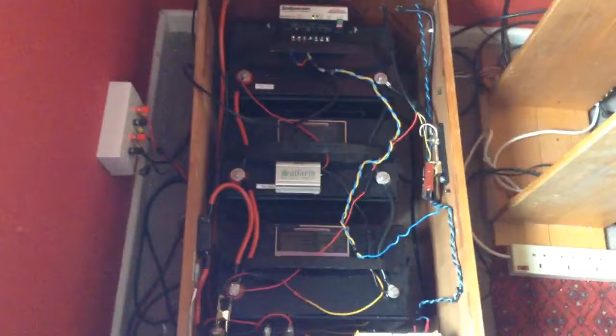So we go down to the battery bank, down here, and this is my battery box. You'll note that this battery box is indoors. It's in the house. So some considerations here. Since the battery box is inside the house, that is a no-no to flooded lead acid batteries, the ones with the vent caps where you add water. As when you charge lead acid batteries, a byproduct is hydrogen gas. That's the bubbles that you see in the liquid when you're charging them. Hydrogen gas is highly flammable, and if it builds up can be explosive, so the place for lead acid batteries is outside. I would only use flooded lead acid batteries if my battery box was outside and well ventilated.